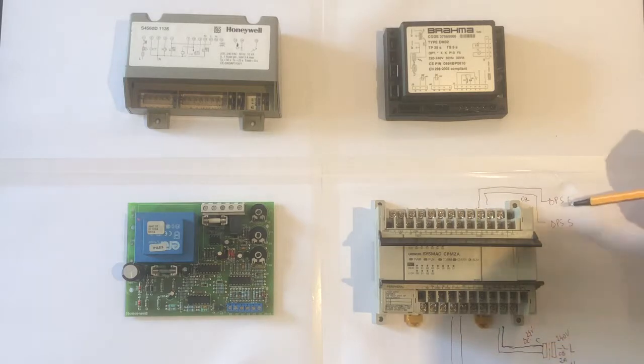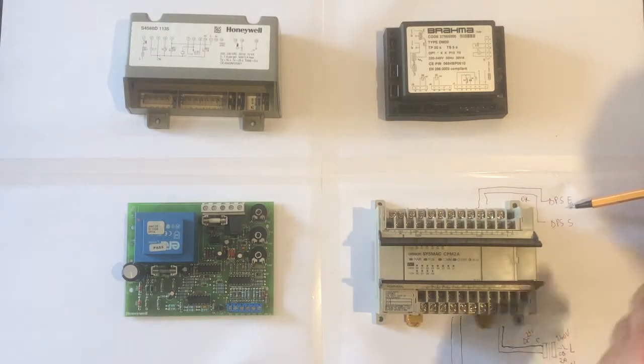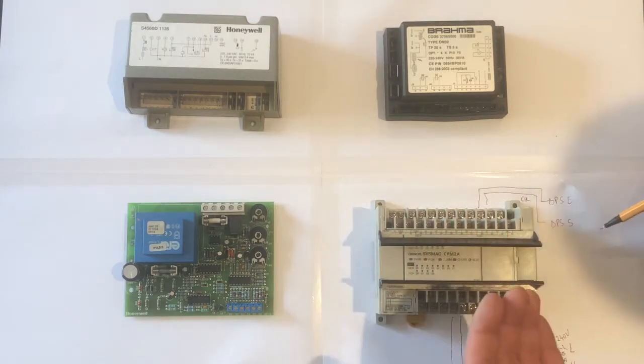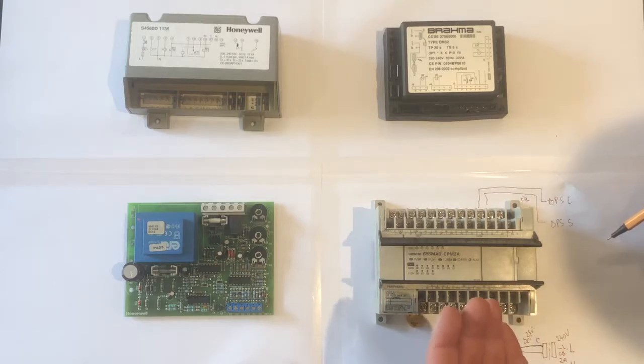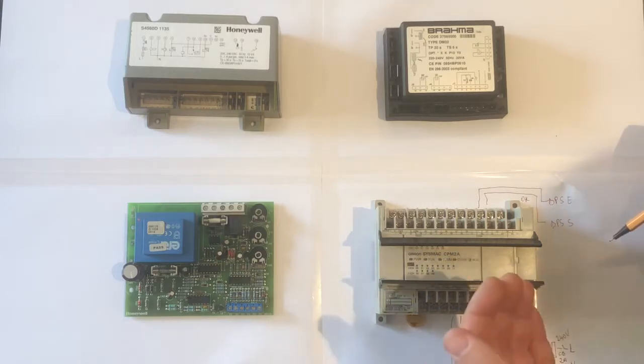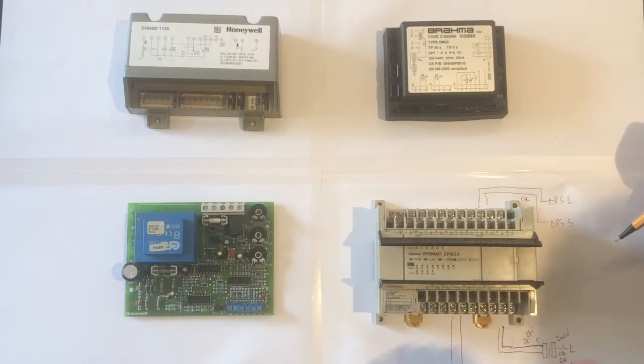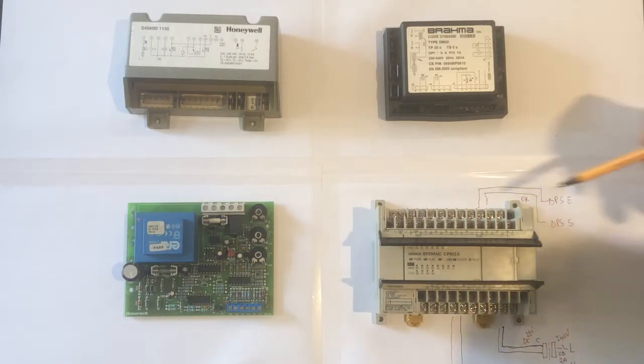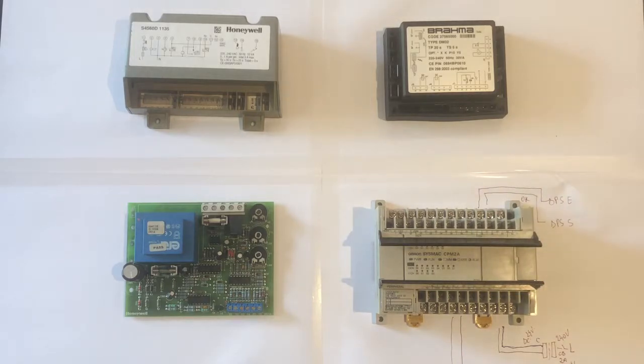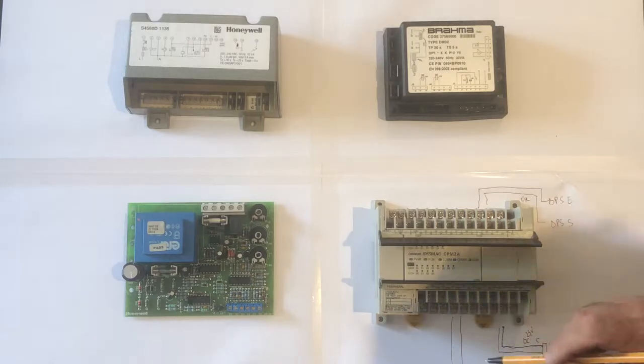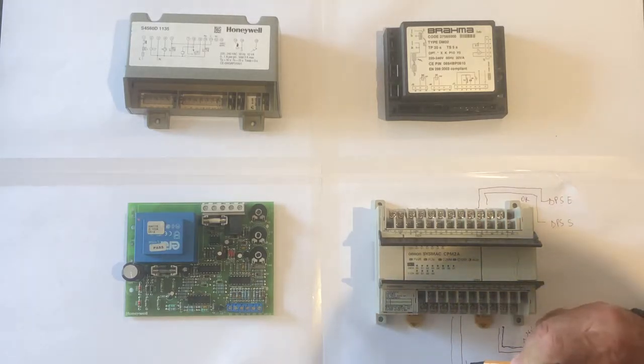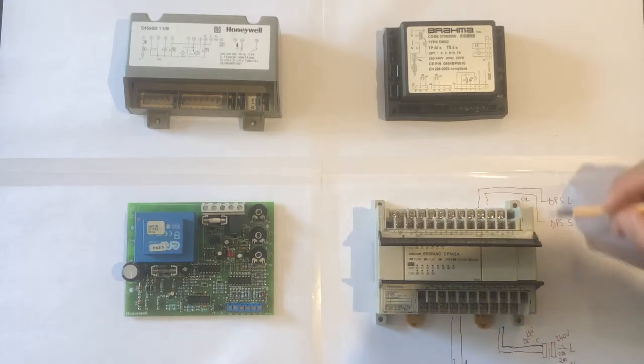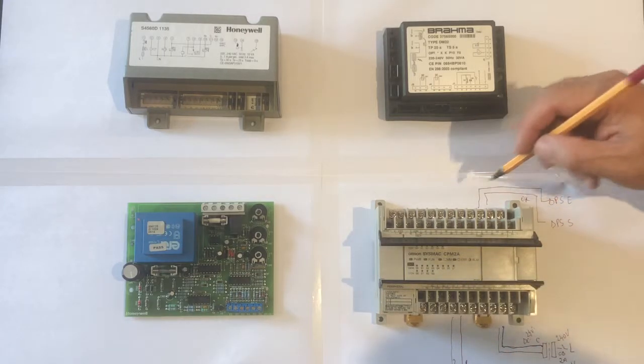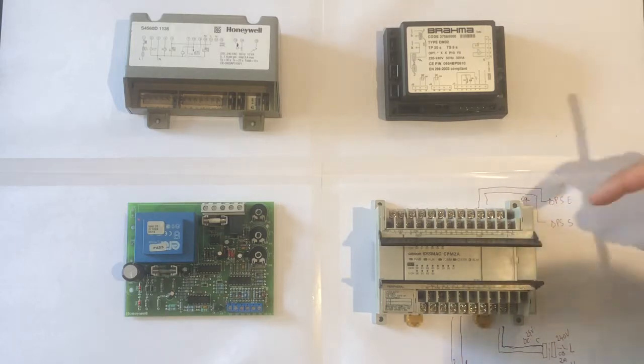So the fan starts, the DPS sends the air flow, and it will say it is okay, because it's pointless to run a gas burner with tubes, a radiant gas burner, if the air is not passing through the tubes. You'll overheat the system, but it's not even working because it is integrated onto the BMS. It can be integrated on a relay, but let's say it's integrated on the BMS. So number one will start the supply fan, number two the extractor fan, then the DPS will send the information back into the BMS. It will tell you it's okay.